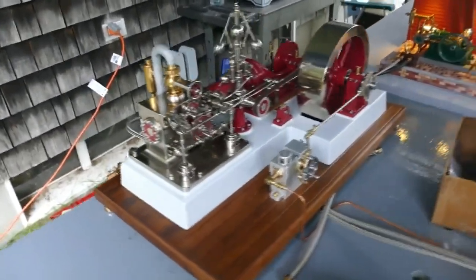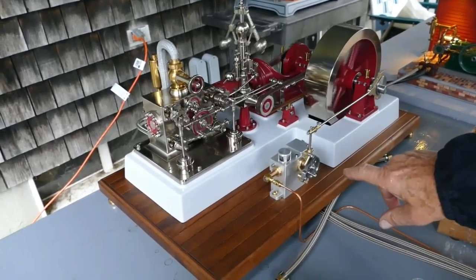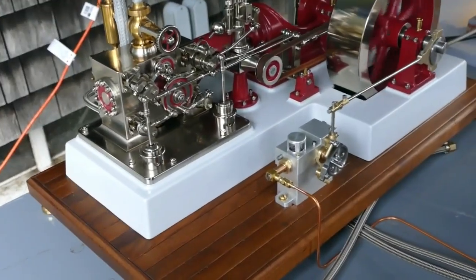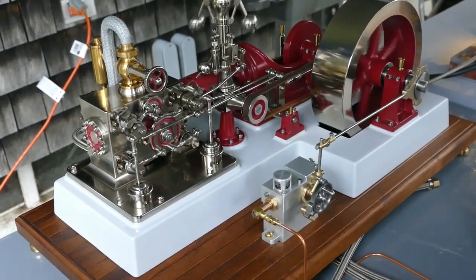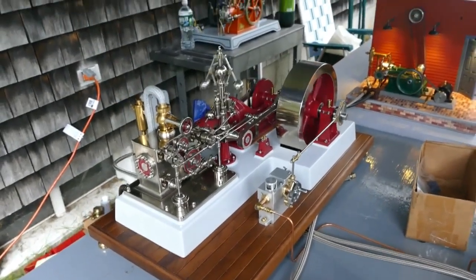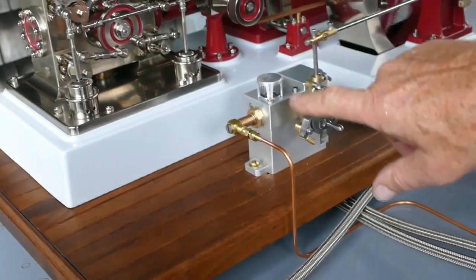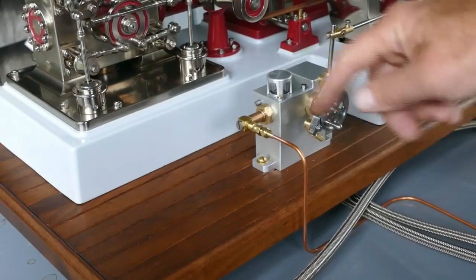Over here we have a Corliss type engine with the rotary valves that operate a forced lubricator. It's a replica of a Manzel lubricator that's on one of the engines inside the building, that forces steam oil back into the steam line to keep the cylinders lubricated. You can tell how much oil goes in by that little sight glass — there's a little drip tube there that you can adjust the amount of flow that goes into the outlet pipe.